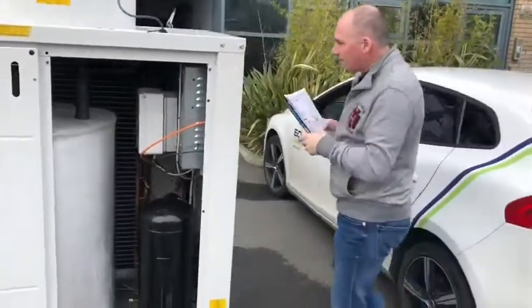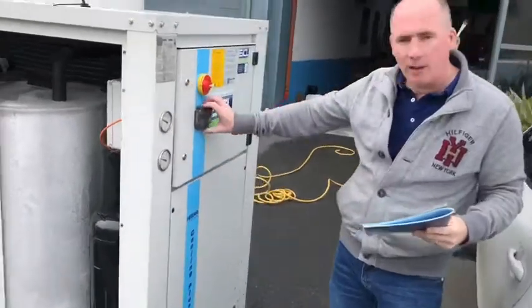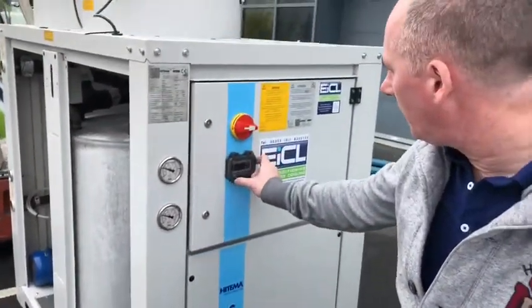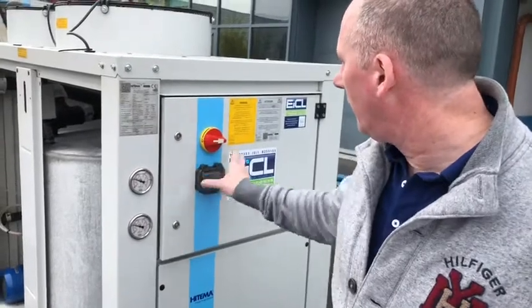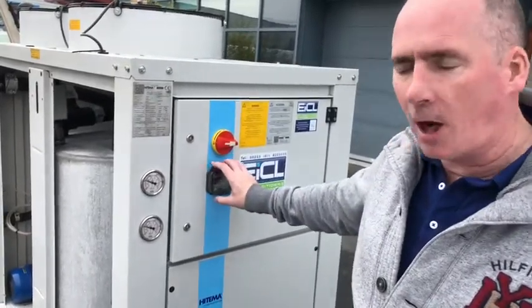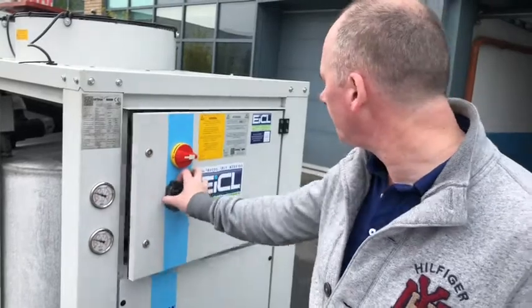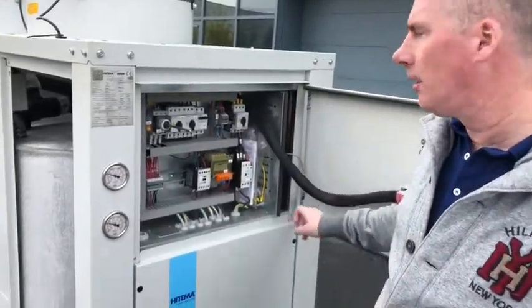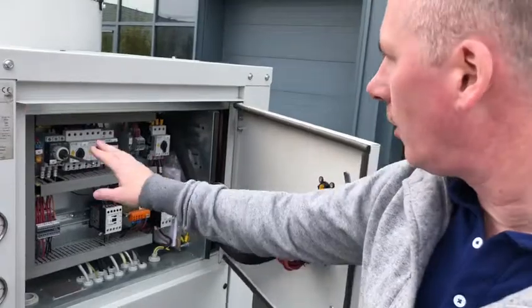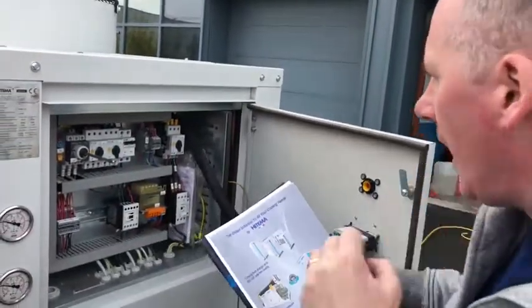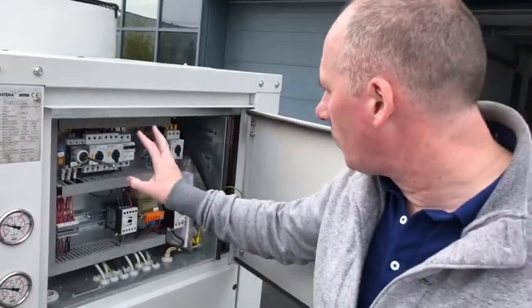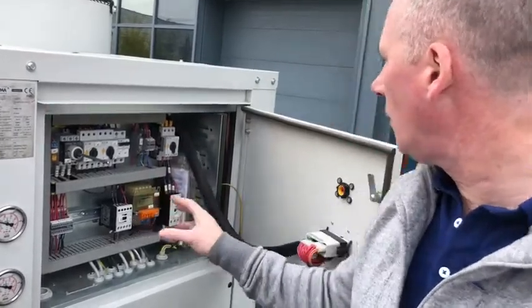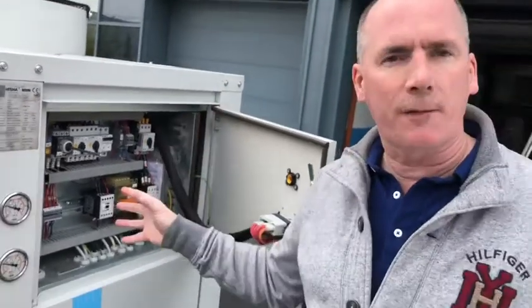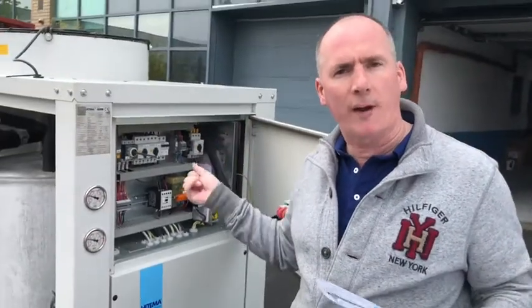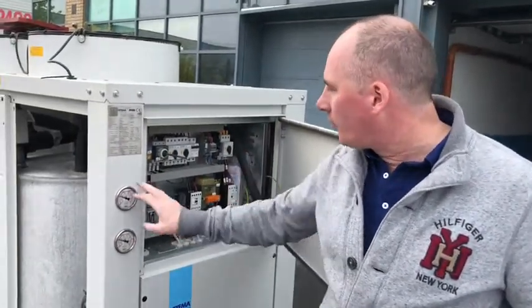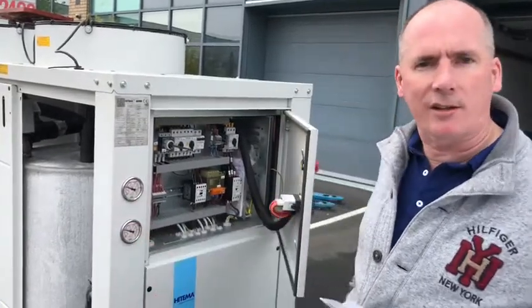Just give you a quick look. So they come with a nice neat Carel controller, it's a micro chiller 2 type, which would be very common in the field. A lot of service engineers are familiar with them. Nice neat control panel. So you have your door electrical isolator, your interlock, you have your compressor overloads, your fan overloads, all the usual controls. You can interface with a BMS remote on off and common alarm, and you have your refrigerant gauges, high pressure and low pressure as standard.